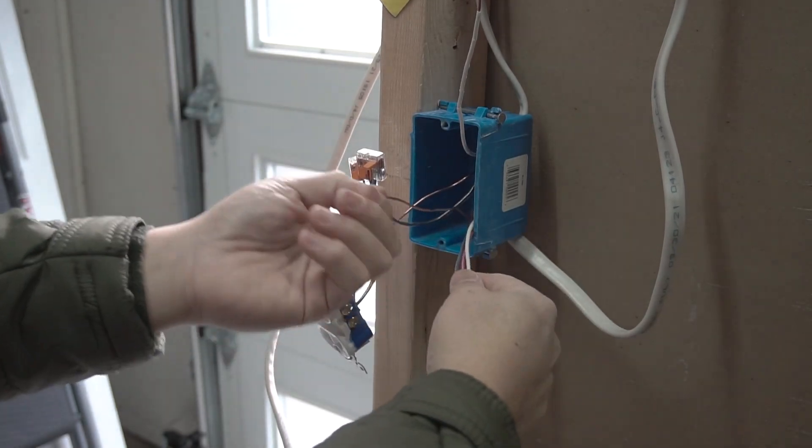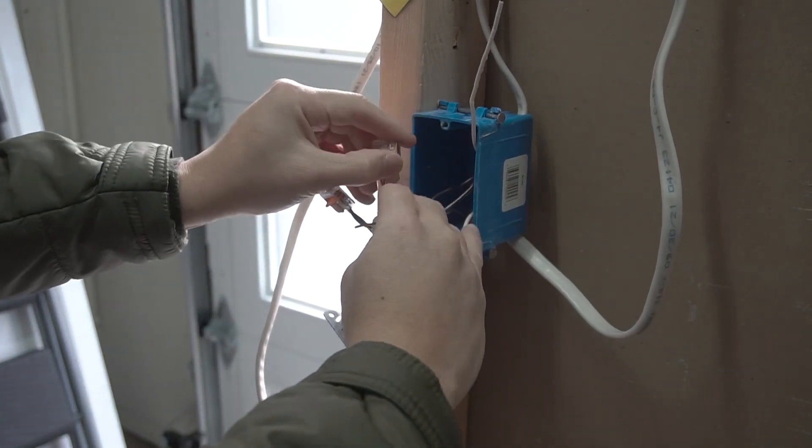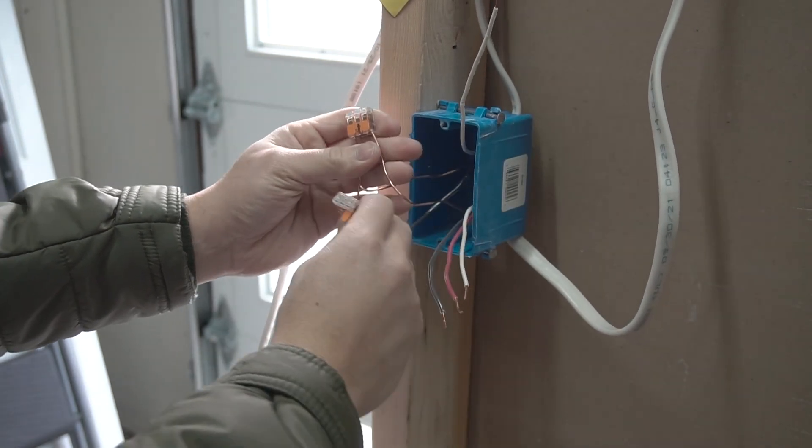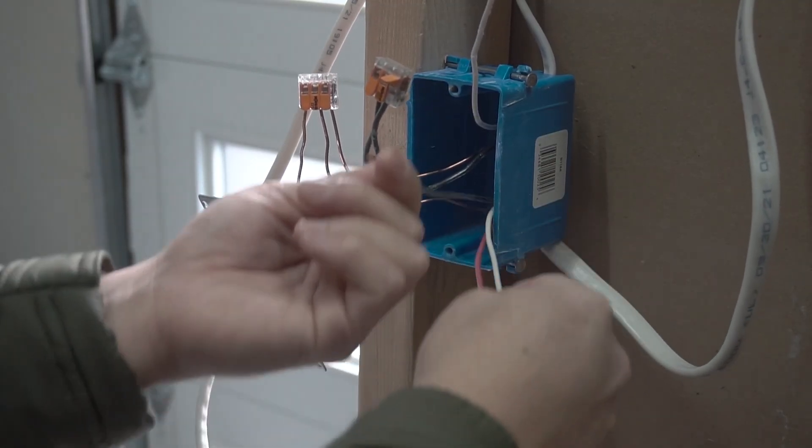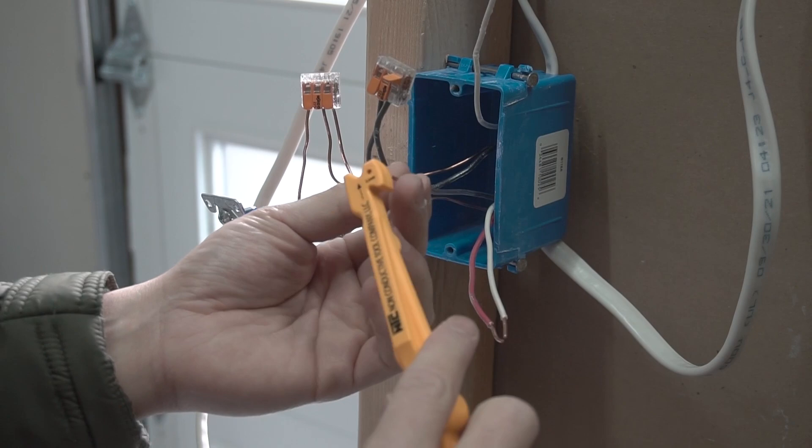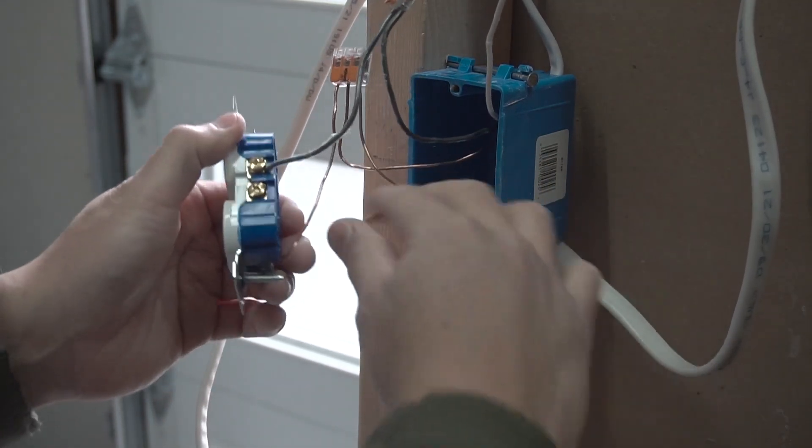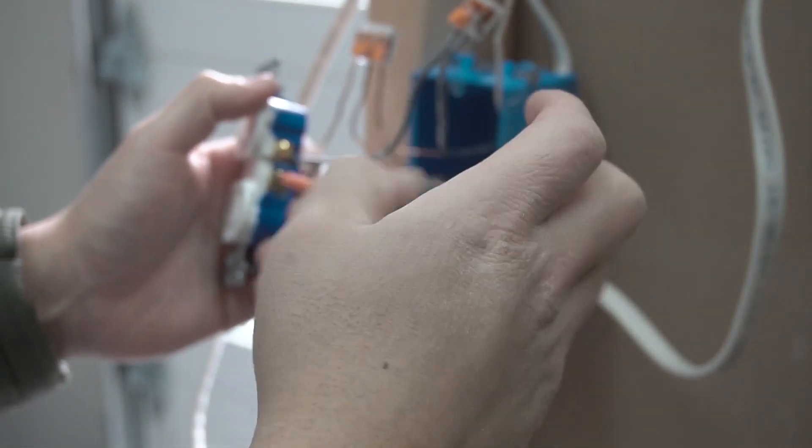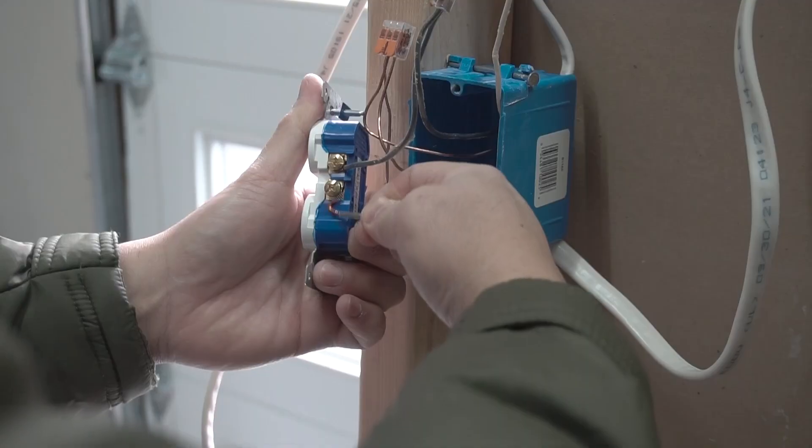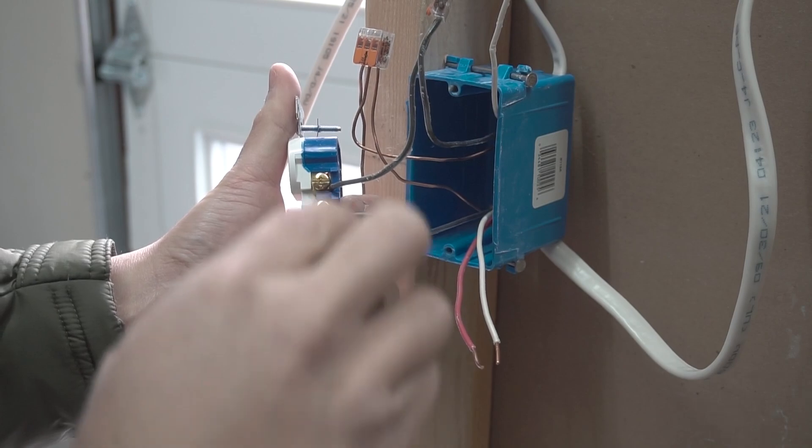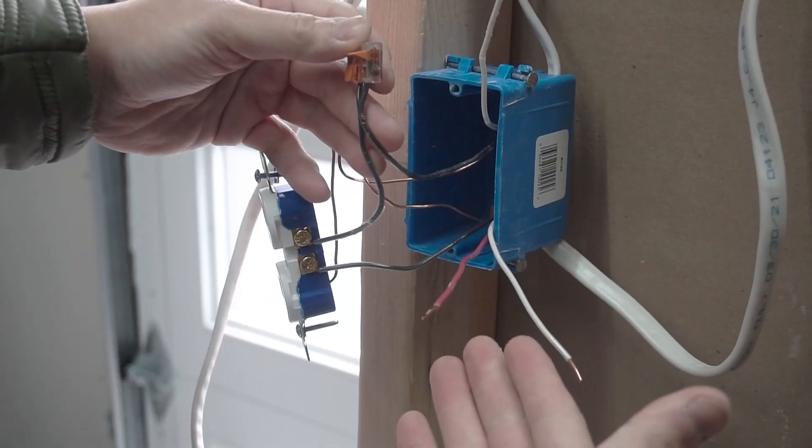So let's start off with the easy part. Take the ground from the 14-3 and attach it to the last lever nut where all the grounds are connected. Don't worry, we're going to go over this one more time again. Now this is very important. Take the black from the 14-3, make a loop, and we're going to attach that onto the bottom terminal. Put that in a clockwise manner. Tighten that down real well.